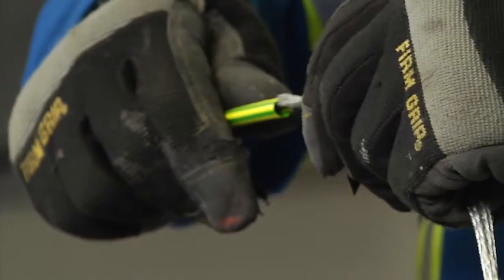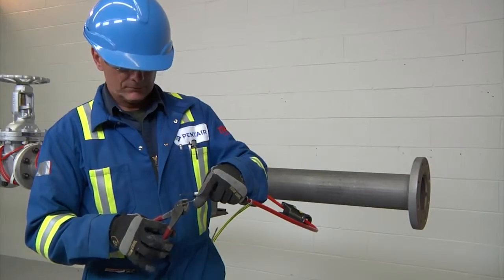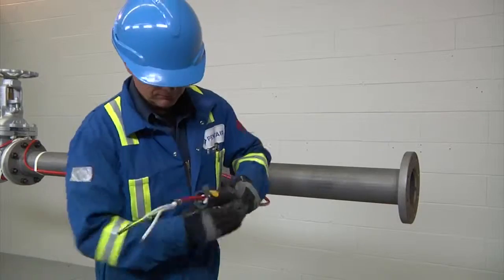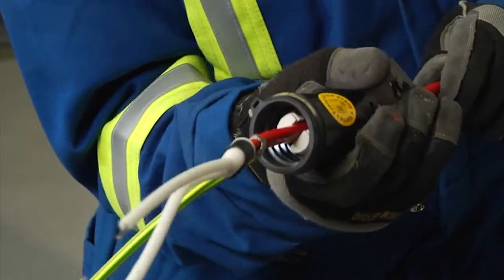Slip the green-yellow tube onto the braid. Trim bus wires and braid, leaving half an inch (13 millimeters) protruding out. Pull the heating cable back into the gland so that one inch (25 millimeters) is exposed.